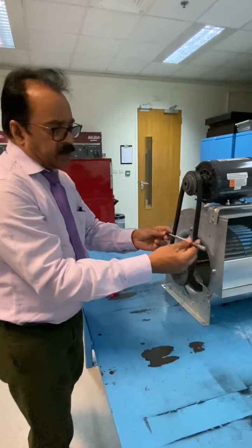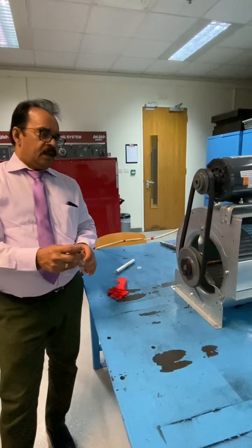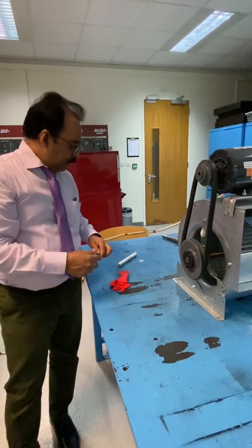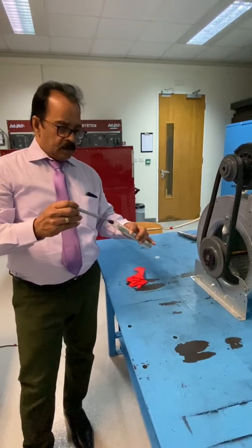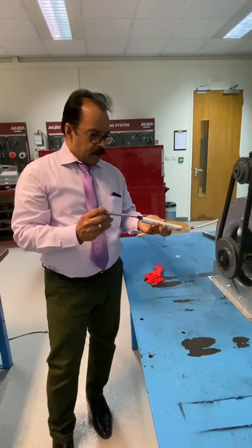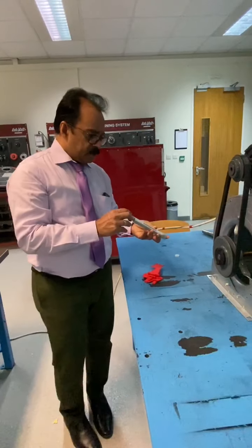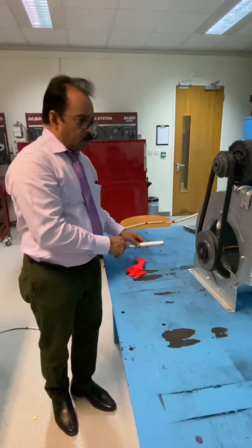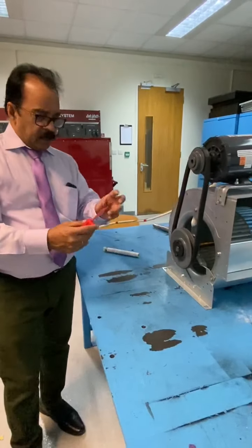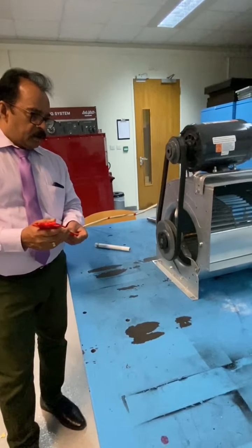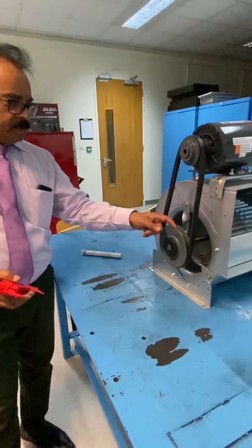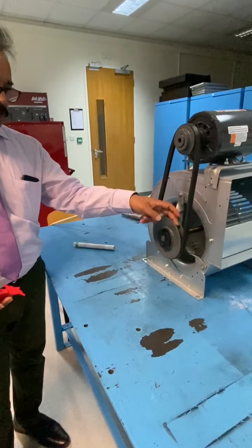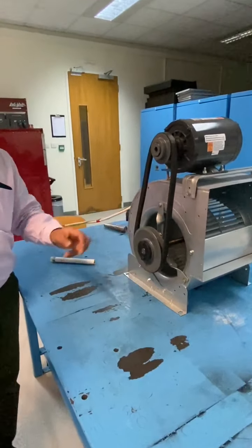This tension gauge will give you the reading, and check with the manufacturer's catalog and make sure that it is maintained, that it has got the proper tension. If it does not have proper tension, it will affect the performance of the blower. Also, after long use, maybe there is too much wear and tear of the groove here, of the pulley. So we can test this one.